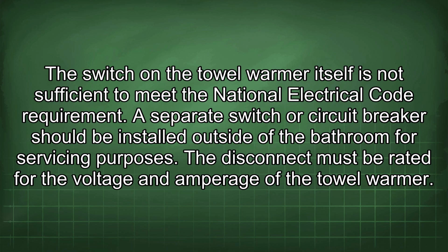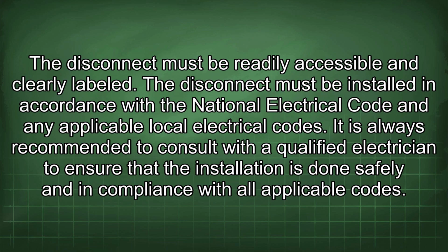A separate switch or circuit breaker should be installed outside of the bathroom for servicing purposes. The disconnect must be rated for the voltage and amperage of the towel warmer. The disconnect must be readily accessible and clearly labeled. The disconnect must be installed in accordance with the National Electrical Code and any applicable local electrical codes. It is always recommended to consult with a qualified electrician to ensure that the installation is done safely and in compliance with all applicable codes.